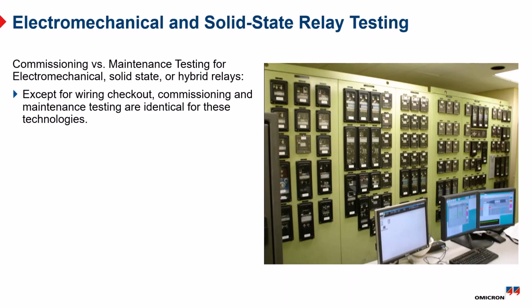For any of these devices, because you have specific functions that are tied to specific components in the device, the commissioning test and periodic maintenance test are really the same. Whether you're putting the relay in for the first time, you run through all of the testing that was in the manual, and then at that time anyway, every 3 years was a typical time frame. You would retest the relays and run basically the exact same test again, because each one of those functions had individual components, and of course there's no self-monitoring or anything like that on these.